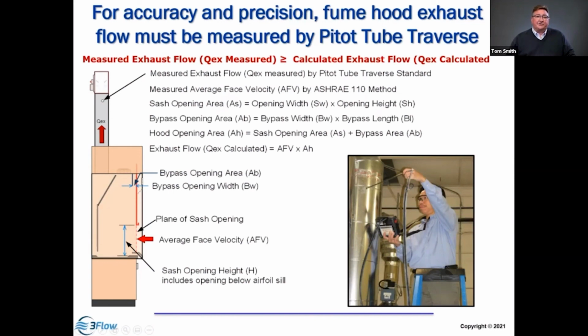But the flow measured in the duct is the accumulation of all that flow. It's the flow of the face plus the flow through the bypass. So the flow of the duct should be at least up to 5% greater than the flow measured through the face. If that's not true, if you come in and you measure 100 feet per minute, 10 square foot opening, and you get 1,000 CFM, but the balance measures 900 CFM, something is wrong. The flow of the duct has to be greater than your calculated flow, or something's wrong.